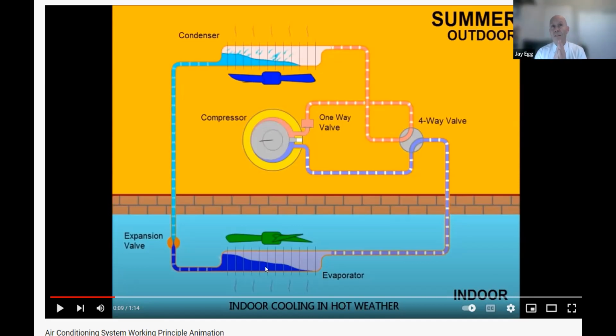In the evaporation process, just as a human being sweats on their hands, that sweat gives a cooling effect as it evaporates, that's the same thing that happens in a refrigeration system. As the refrigerant begins to evaporate, we get a cooling effect, and the evaporator absorbs tremendous amounts of heat while it's cooling, and that evaporation of that refrigerant then leaves a cool, low temperature gas that returns to the compressor, and it is compressed and becomes a high temperature, high pressure gas ready for condensation again.